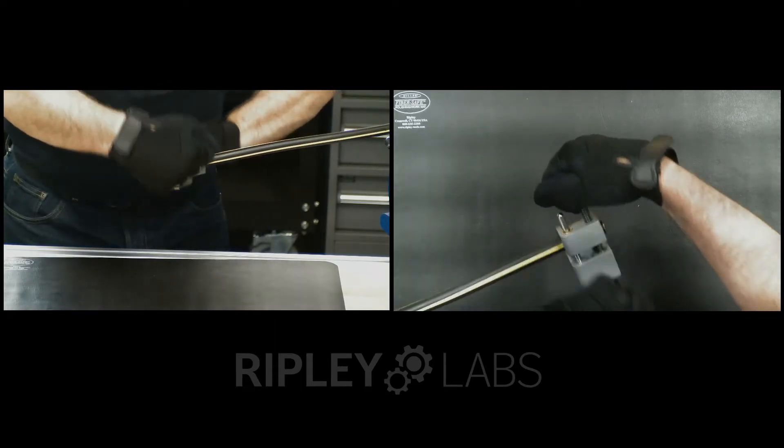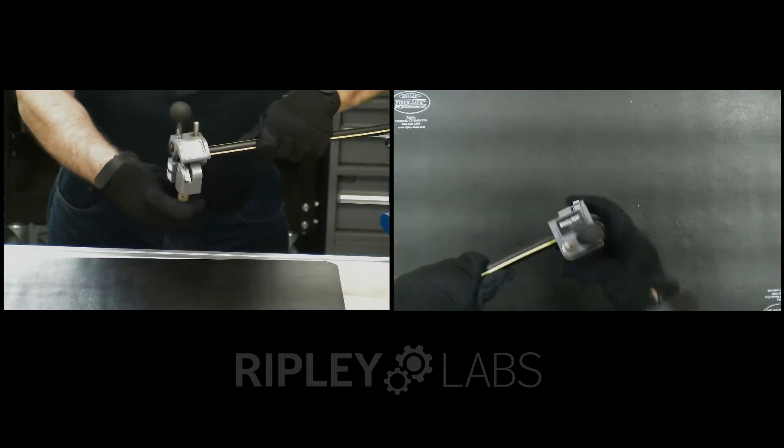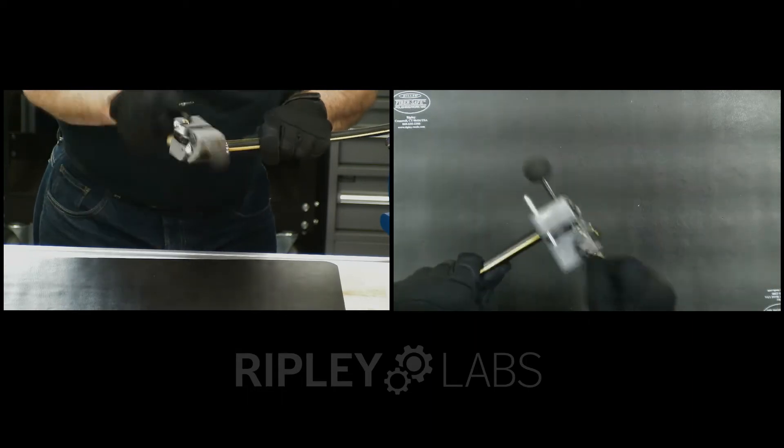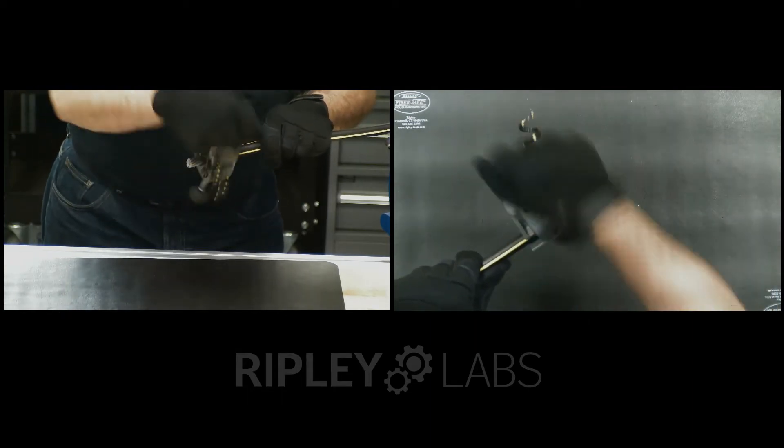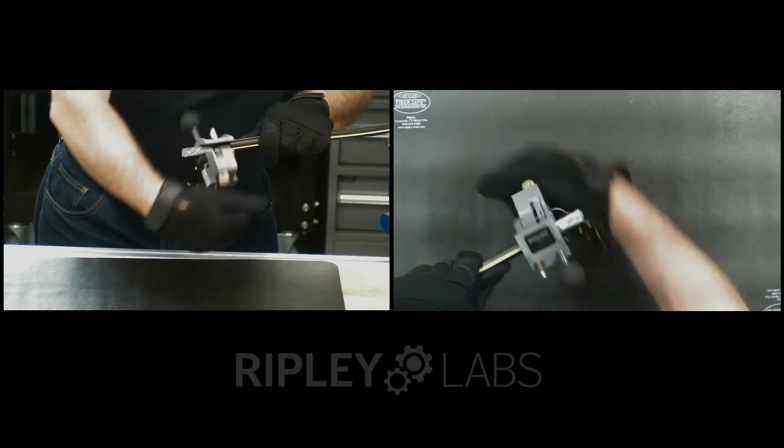Four clicks was used for this 4-0-80 mil cable. Start rotating. The blade will start cutting and the tool easily feeds itself along the cable. The ergonomic handle and stable platform make quick work of longer strips.